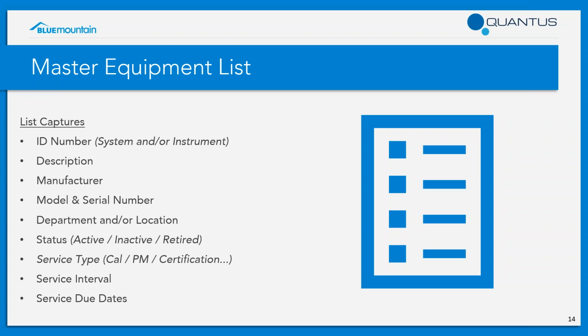And in a master equipment list, we're typically going to talk about keeping it simple with items listed here on the slide. So the first one we have listed is an identification number. That's clearly important to understand what equipment is due for calibration and lives within your facility. And if you're using a parent-child relationship, which we'll talk about later, you can choose to include both ID numbers or just the single child ID. When you're covering your descriptions, you're going to want to really do your best to keep your descriptions simple and consistent, using things like temperature transmitter or pressure gauge for all those various instruments. And you're going to want to try to avoid over-descriptive nomenclatures. It could really be inconsistent throughout the system.